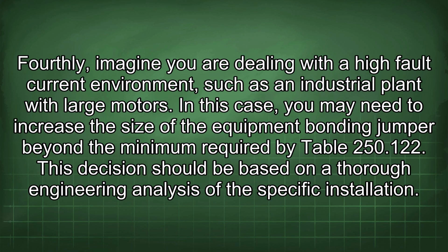Fourthly, imagine you are dealing with a high fault current environment, such as an industrial plant with large motors. In this case, you may need to increase the size of the equipment bonding jumper beyond the minimum required by Table 250.122. This decision should be based on a thorough engineering analysis of the specific installation.